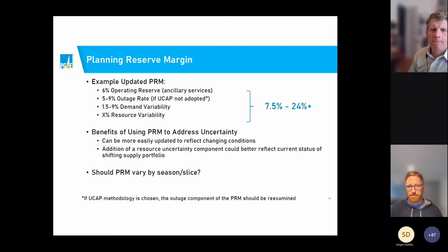But PG&E's proposal is actually to set a reliability planning standard, 1 in 10, 1 in 20, something like that, do an LOLE and actually determine PRM based on an LOLE. So, Peter, that's what I think I heard in your response. Brent, I think that's sort of what our general thinking is. I think we're open as to whether or not that is a sound way of doing it, but that's sort of what our current thinking is.